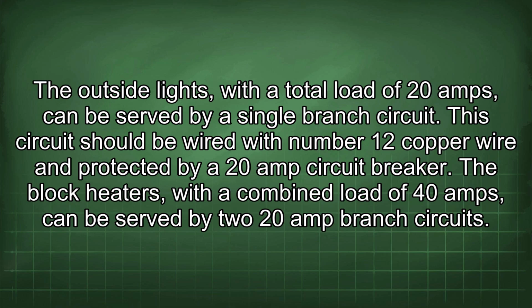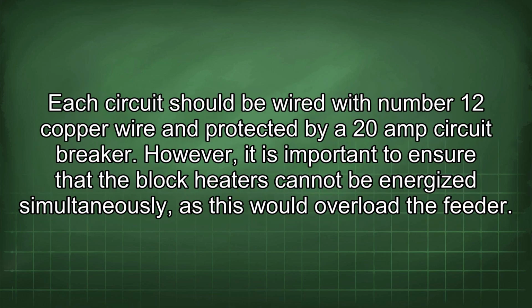The outside lights, with a total load of 20 amps, can be served by a single branch circuit. This circuit should be wired with number 12 copper wire and protected by a 20 amp circuit breaker. The block heaters, with a combined load of 40 amps, can be served by two 20 amp branch circuits. Each circuit should be wired with number 12 copper wire and protected by a 20 amp circuit breaker.